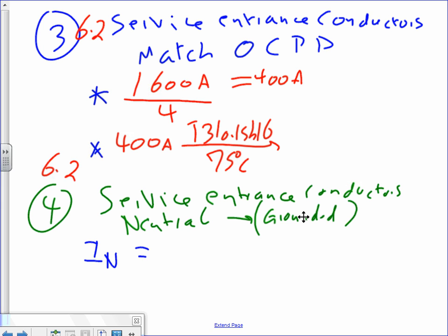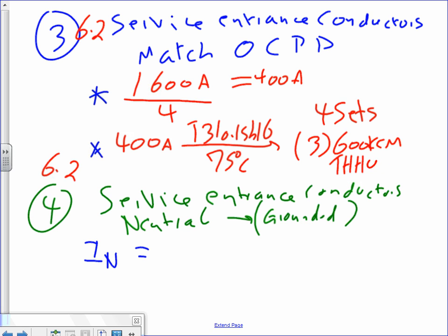Okay, so what size conductor? Here's how we write it. I have 4 sets. Everybody knows what a set is? Gentlemen, you're looking at a set right here. Here's a set. That's called the set. Can you guys see it? Set. 4 sets. Each set is going to have how many conductors? 3 conductors, 600 kcmil THHW. This is your S.